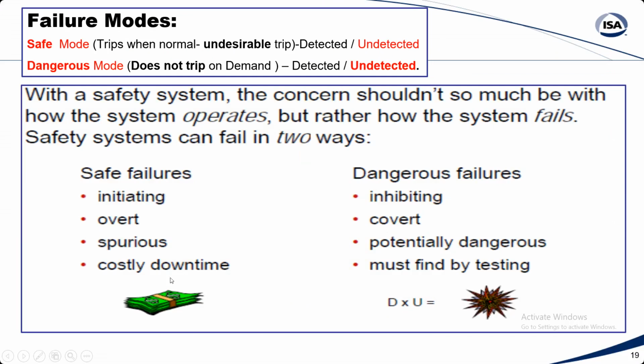You lose the money. But in case of dangerous failure, it is inhibiting. That means it's not so easily visible. It's not obvious. Okay, it is hidden. Potentially, it is dangerous. That means it can lead to a big disaster. That is why a dangerous failure can lead to dangers. Means your level transmitter, even if it is SIL rated, if it fails, it is a dangerous failure. And how can you find it?